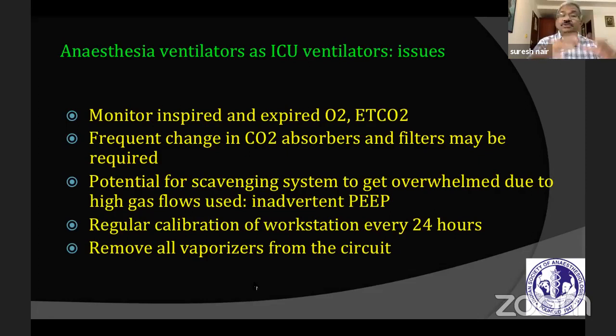When you use such high flows, especially in theaters with a scavenging system, the scavenging system itself can get overwhelmed. The normal scavenging system's ability is about 80 to 130 liters, if I remember correctly, that much air can be removed in an operating room. But when you use very high fresh gas flows, this scavenging system can be overwhelmed.